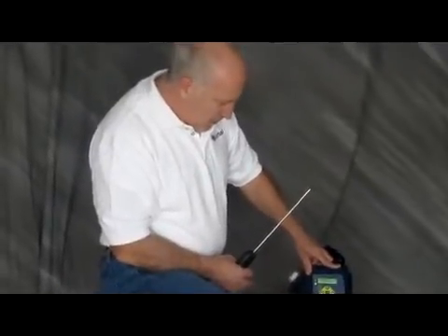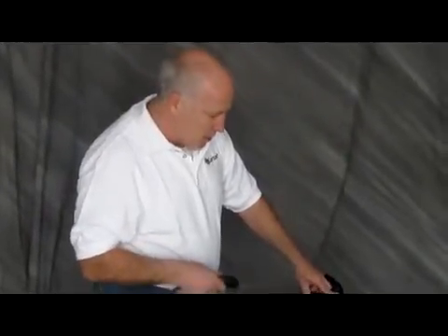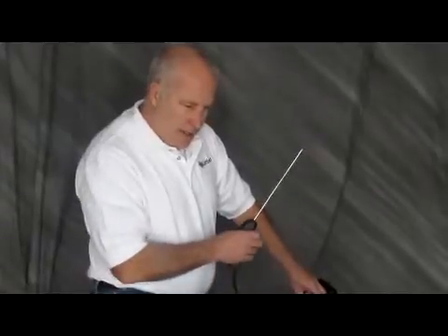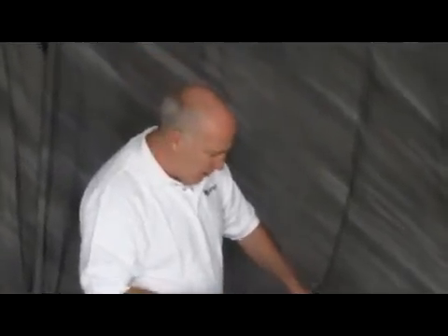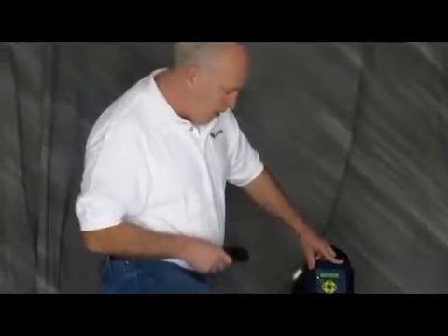I have found with this particular unit, sometimes I get a little drift on it where I'll get a 1 PPM leak when I really don't have one. I haven't seen it on other units, but my particular unit it does. There are ways that at the factory they can adjust the voltages and things to make sure that doesn't happen, and I actually did go through that process, so if you have that problem, let me know.